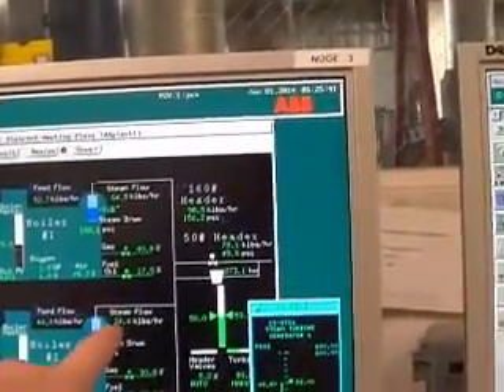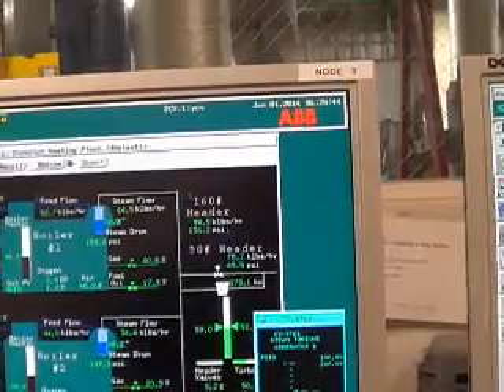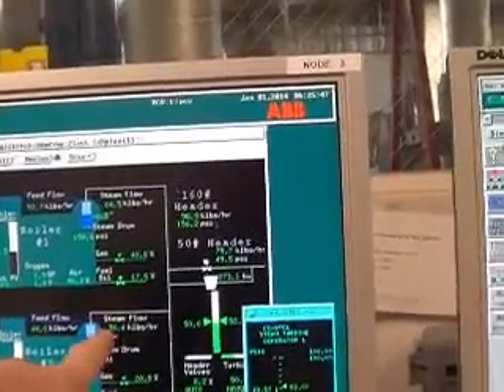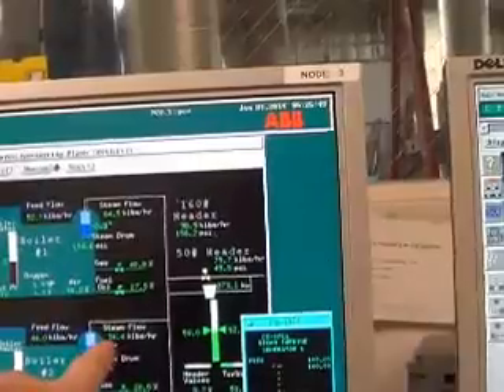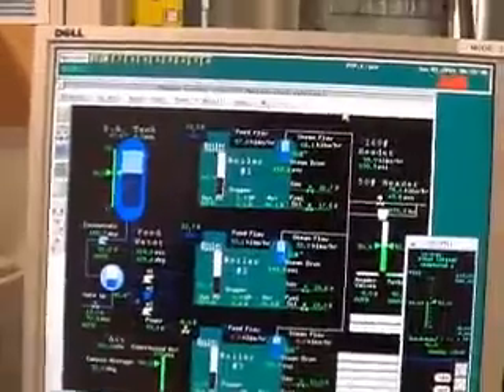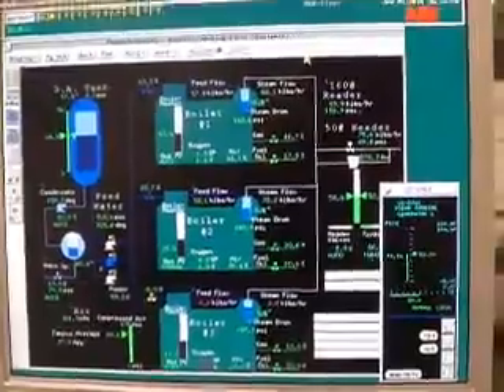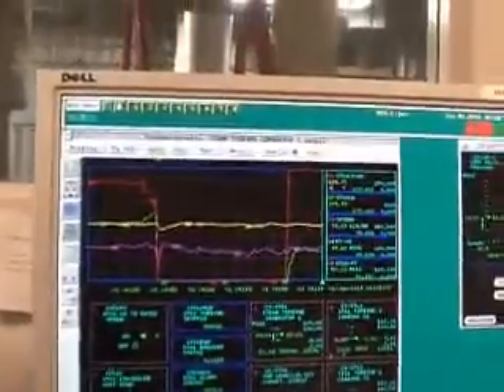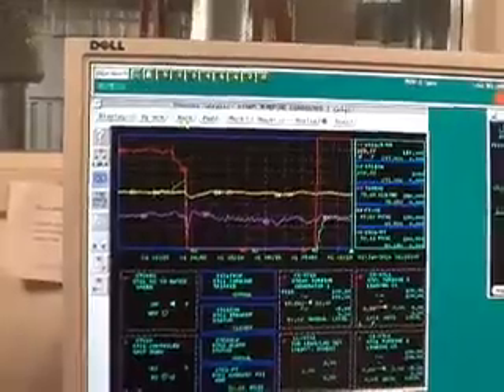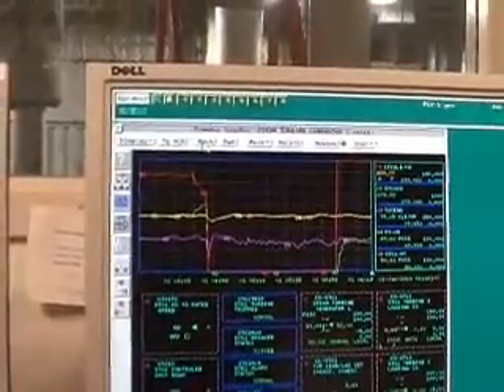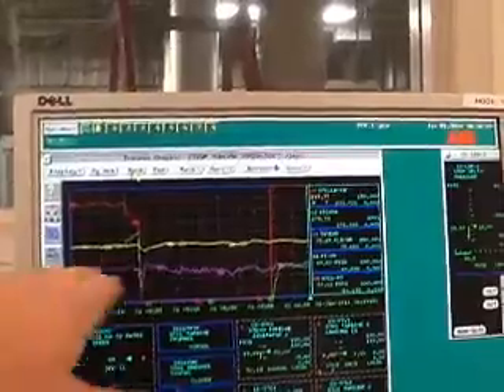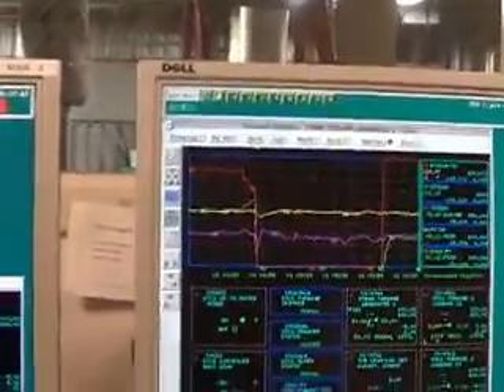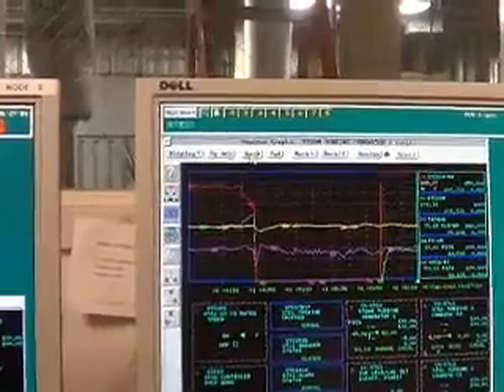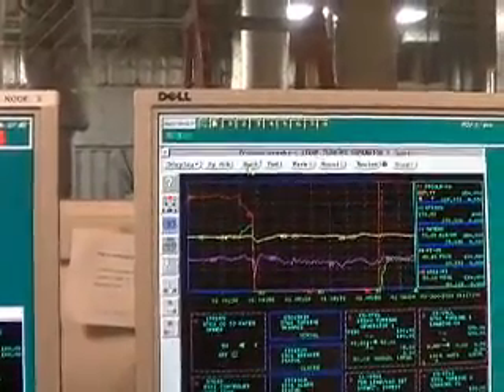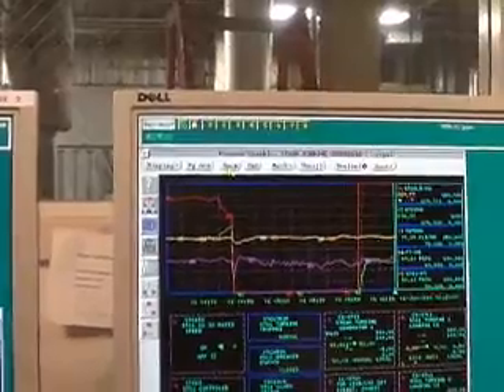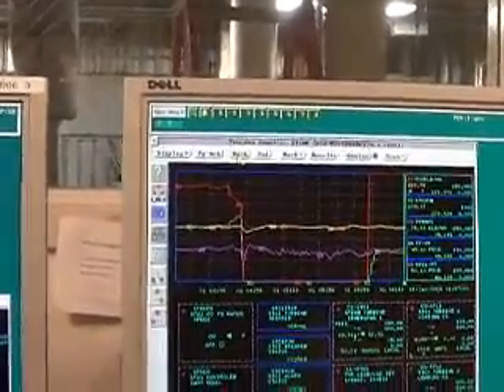Now this is at 20% in manual, and we're making 34,000 pounds an hour of steam. So I can see what's happening. This screen over here will actually document everything I've said. People will be able to look on this. This is producing a trend. It's kind of like the black box in an airplane, so that every keystroke that you make, every change you make to the plant, every event that happens is recorded in the memory of the computer.